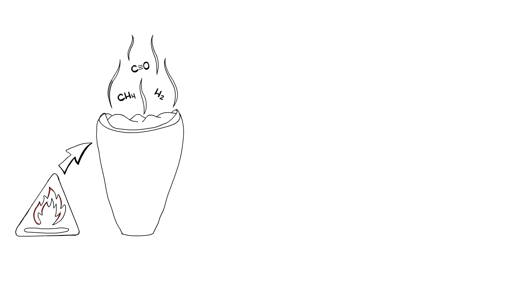What is combustible gas and how is it formed? Combustible gas consists of mainly carbon monoxide, hydrogen, and methane or natural gas. These gases are produced from incomplete combustion in process equipment. Stored wood pellets may also emit combustible gases, especially during self-heating.